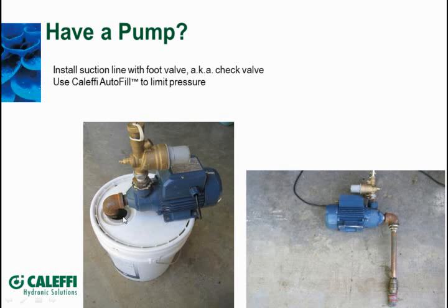So I said, well, if you're pumping out of these 5-gallon plastic buckets, which they are, the solar fluid that we sell from Caleffi comes in these 5-gallon buckets, and I'll just make up something quick and run it over to you that you can use. And so I just took that little half-horsepower pump, put a little check valve on the bottom of it, just some stainless steel screen door mesh on the bottom there, and it just sets right on the bucket.